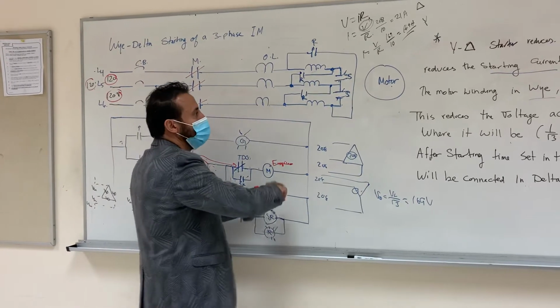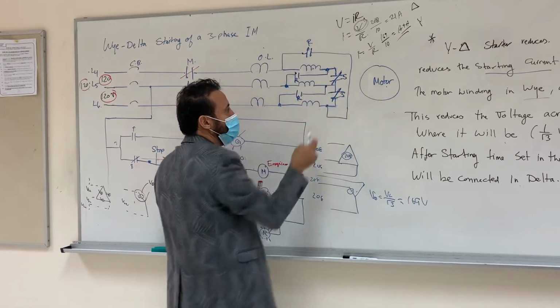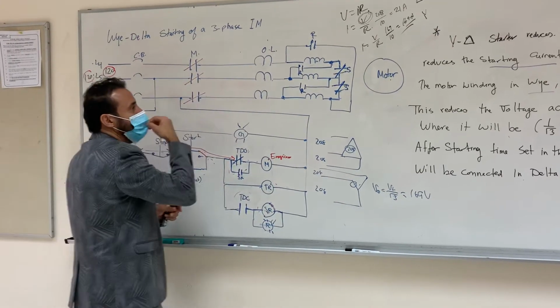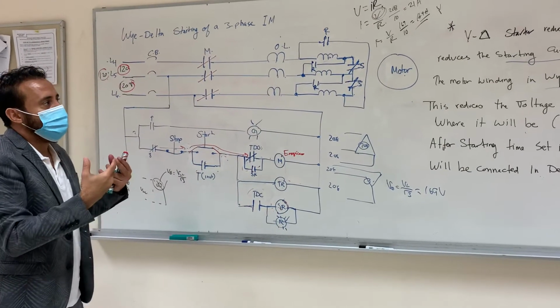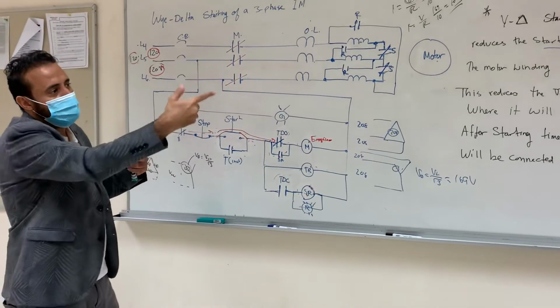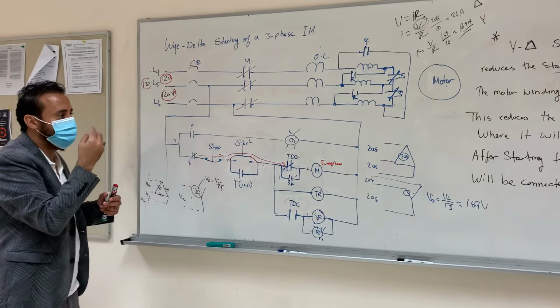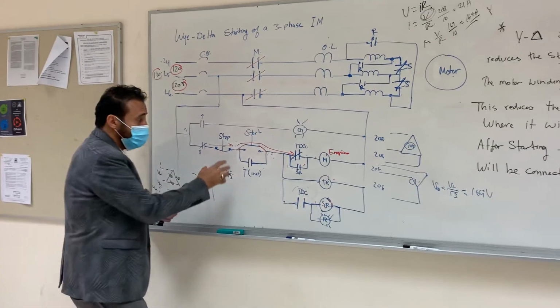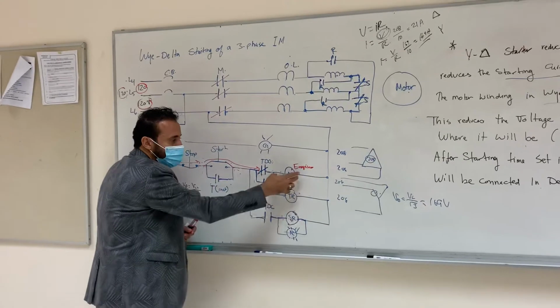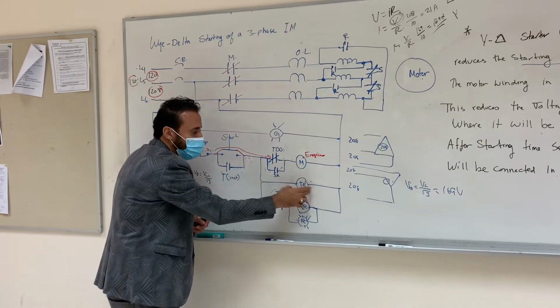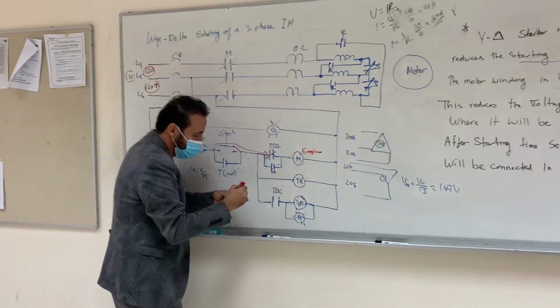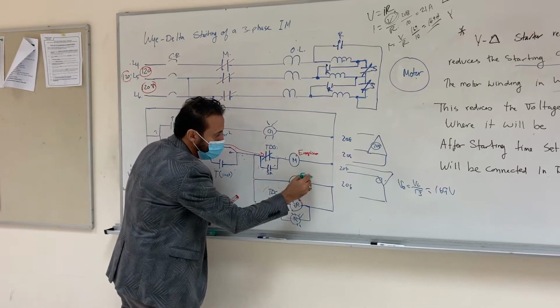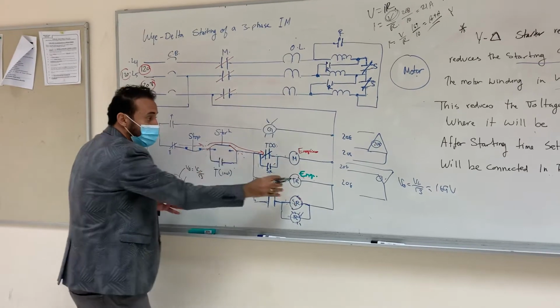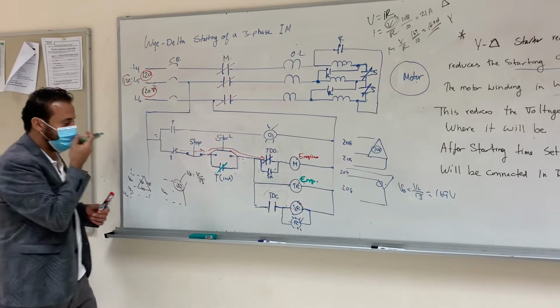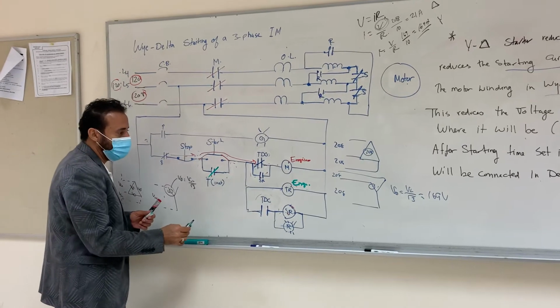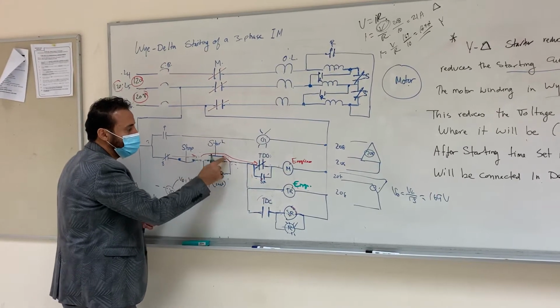Actually, guys, this one here is normally open also, initially normally open. So when this is closed, the motor will run with the Y connection, because as we explained there, we want the current to be very small, very tiny. While we do this, this time relay is parallel to this contactor, so it will be energized also. So this will be energized. This will be energized. So when this is energized, immediately it will close this, because this T instant is with the time relay. So now you can release your finger.